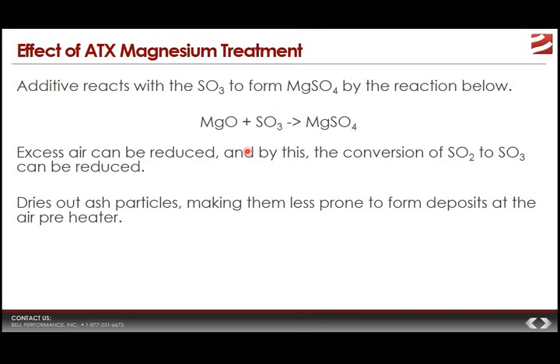One of the benefits of ATX is that it not only attacks corrosion, but it also helps the operator reduce excess air. ATX contains not only magnesium but also organometallic combustion catalysts that help the operator achieve the same combustion level as before with a lower oxygen level being supplied. This is very important — if you can get the same combustion with less oxygen, you're going to have less SO2 being oxidized to SO3, which is really going to help your corrosion problem. The magnesium in ATX also changes the melting point of ash particles, dries them out, and makes deposits more friable and more likely to fall off.